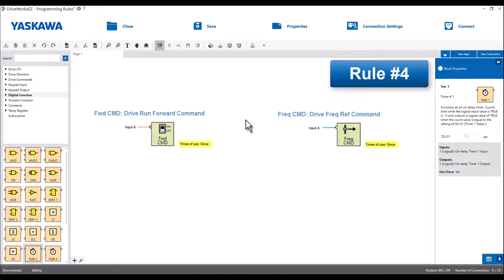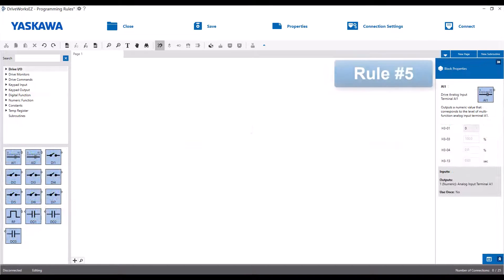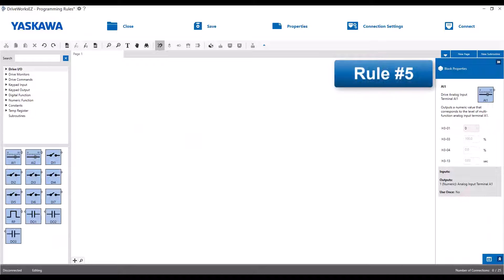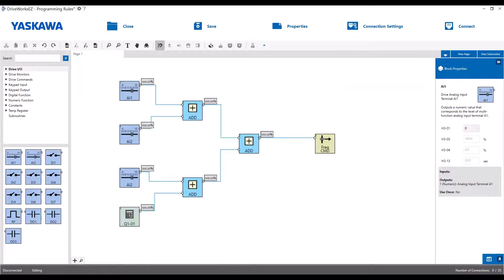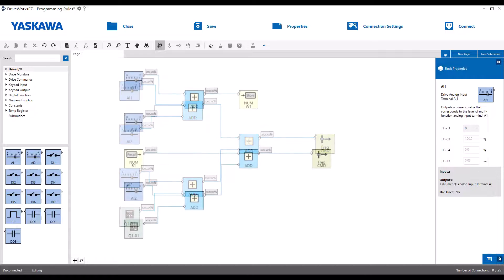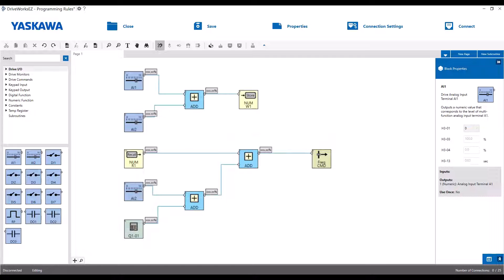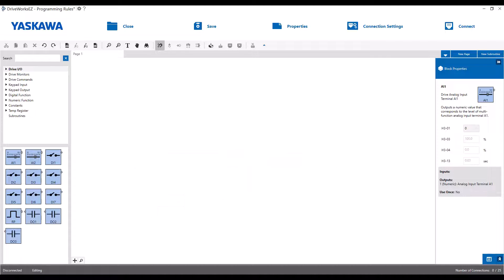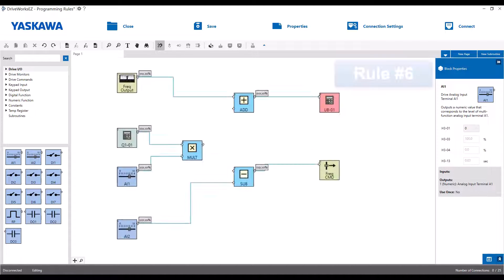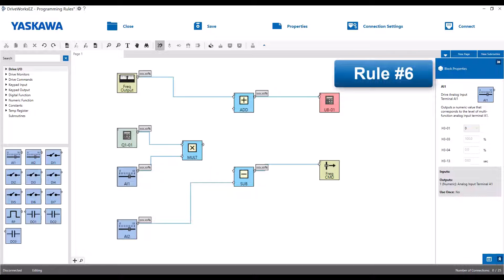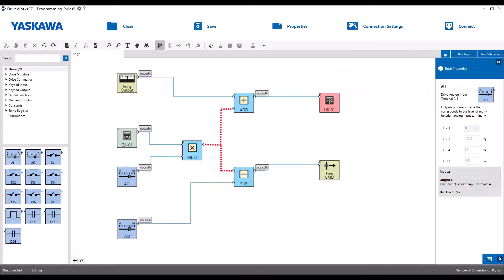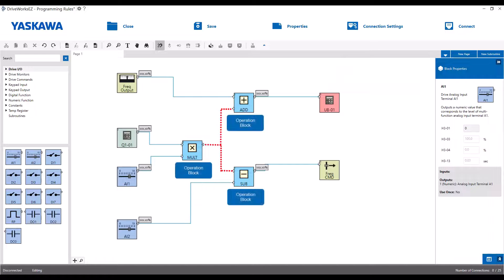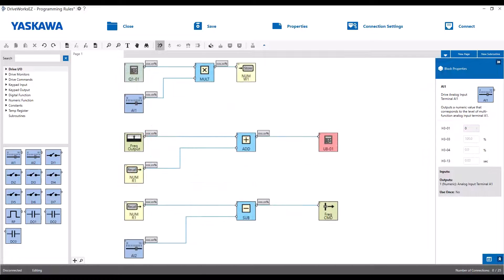Function block outputs cannot be connected to both inputs of the same type of function block. So this one's a little bit confusing to understand if you just read it. But if you look at these pictures, there's the correct and the incorrect way to do it. You can't have two add blocks be the inputs to a third add block. You'd have to use a temporary register in place of one of the add blocks feeding into the third add block. And the last rule is that the output of any block can be connected to multiple output blocks but can only be connected to one operation block. Again, the workaround is the use of temporary reads and writes to achieve your objective without breaking the rule.